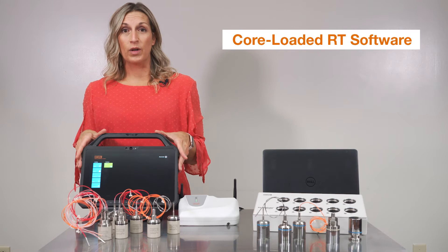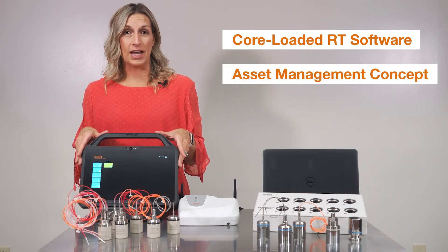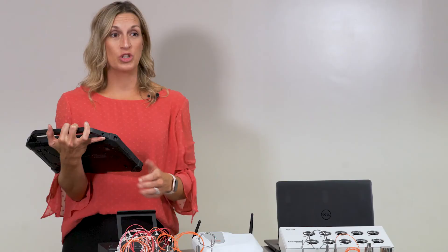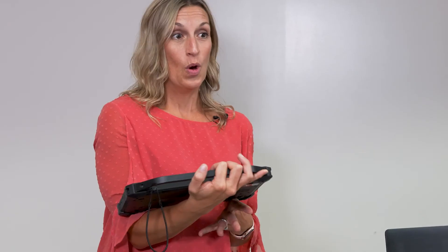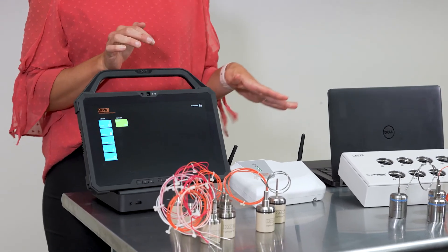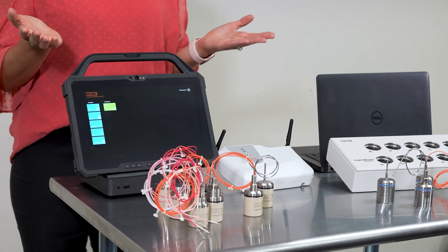This console comes core loaded with the ValProbe RT software. This software has our asset management concept and it's very user friendly. After you start your study, you can disconnect the tablet from the base station, remove the tablet, and bring it back to your desk to do reporting. You could start doing another setup, or if you have another base station and more loggers, you can connect this tablet to that base station and check in on that live data, start the study or stop the study. Once you're ready to come back, you can just dock it back on, connect to the base station, and see what's going on with your qualification.